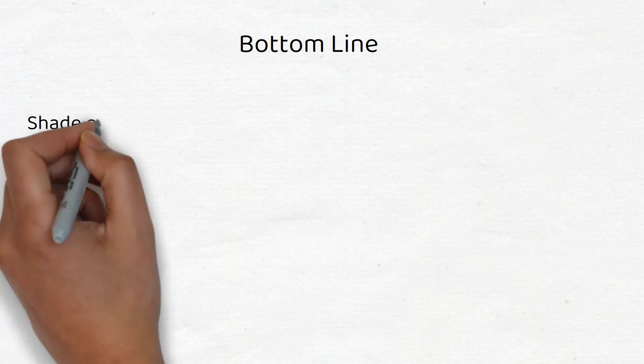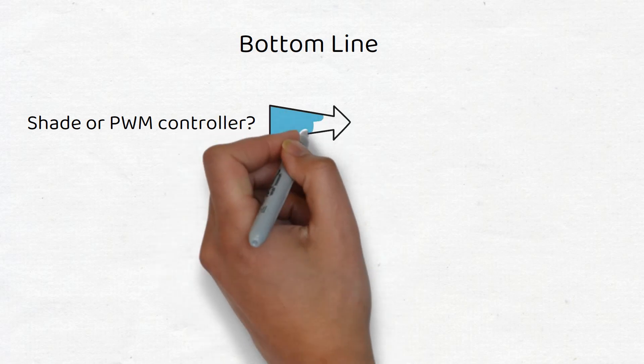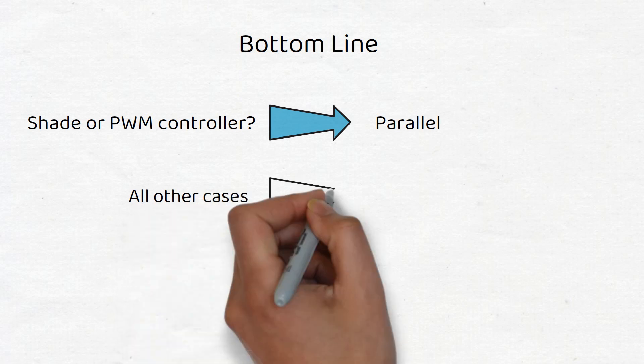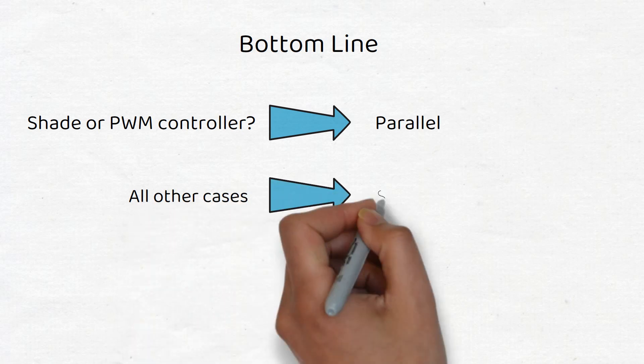Bottom line, if you choose between series or parallel, you have to keep in mind the shading conditions and the type of charge controller you are using. If you expect shading or use a PWM charge controller, choose parallel. In all other cases, go for a series connection.